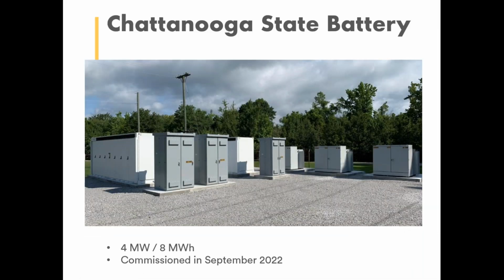This is the last battery project I was going to talk about. This one was not set up to be a microgrid. It was developed primarily for demand reduction. We've got 3 megapacks installed here, 3 disconnect switches, and 3 transformers. Total capacity is 4 megawatts, 8 megawatt hours. For demand reduction purposes, our peak typically lasts about 2 hours, so that's why it's sized this way, to carry us through a typical peak event and reduce demand by 4 megawatts, which at current TVA rates is about $45,000 a month in payback from this system.